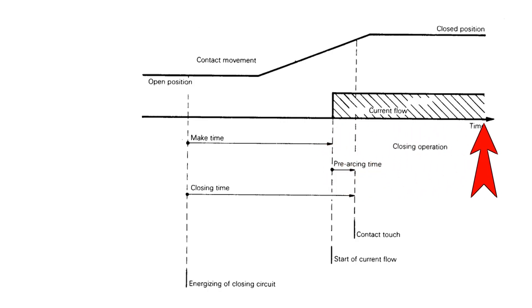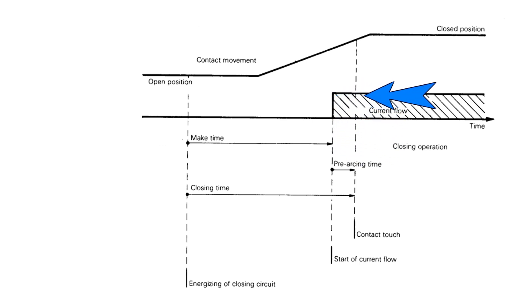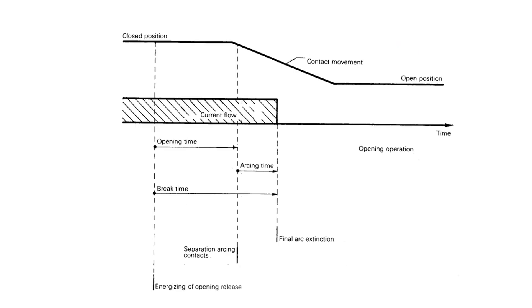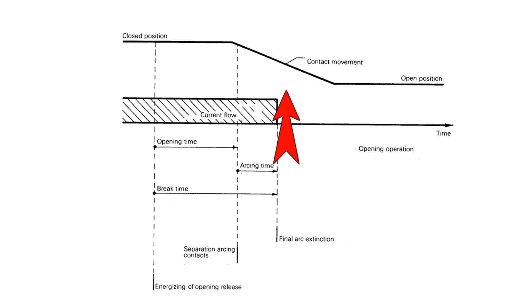Why is this portion called making time? Because during this period, although the contacts have not physically touched, current starts flowing through the breaker due to the arc. Hence, it is called making time — the circuit breaker makes the circuit by allowing current flow even before full mechanical closure. Similarly, breaking time refers to the time taken to completely interrupt current after the opening release is energized, even though the breaker has not yet physically completed its opening operation.